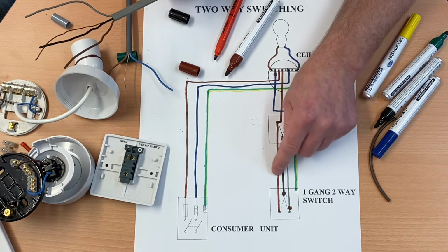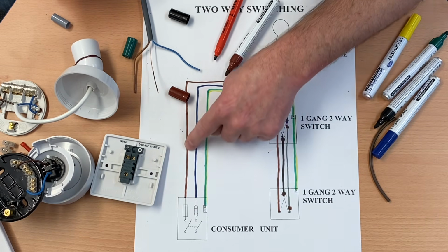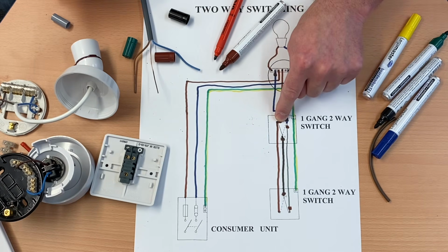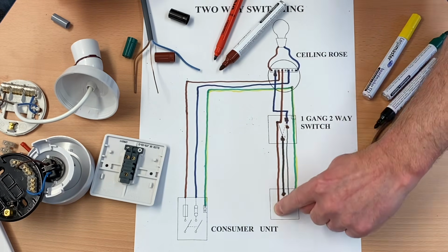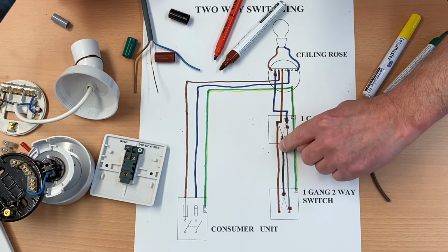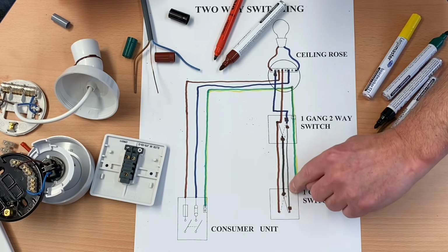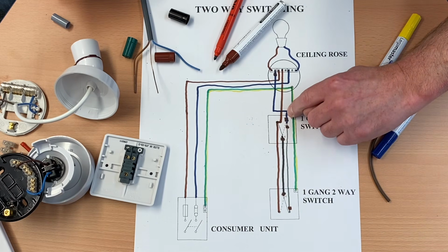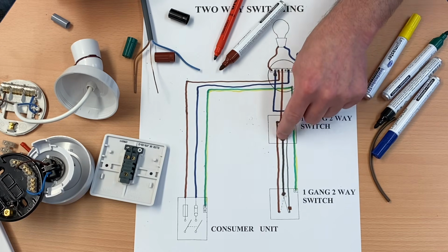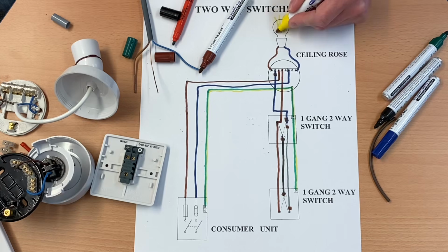So let's follow the circuit through, see if we can work out whether the light fitting is on. So my permanent line connection comes up and into the looping terminal. It comes down to here. It goes down here, but look at the blade. It also goes down this blade here, and the line connection is connected to this one here, this blade here, and up this grey one here, onto the switching line here. And yes, in that position there, with the 2 blades as they are now, this lamp would illuminate. So this would be illuminated at that stage.